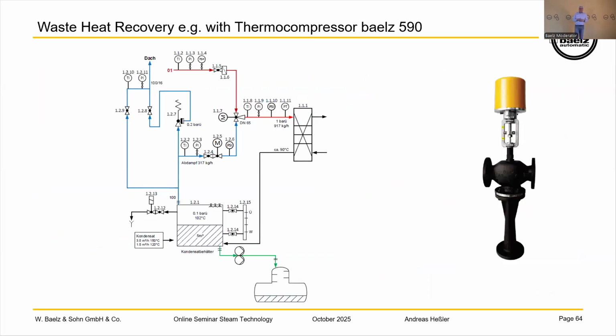Here it is very good to explain. You see our 590. We have the flash, where you see on the top the safety valves, and the flash steam comes. The flash steam will be increased with the motive steam to a middle pressure steam, and this can be used for our heat exchanger. So we really use the heat that you normally lose through the flashing of the steam, which normally goes over the roof. You are using it to heat up your secondary side on the heat exchanger.